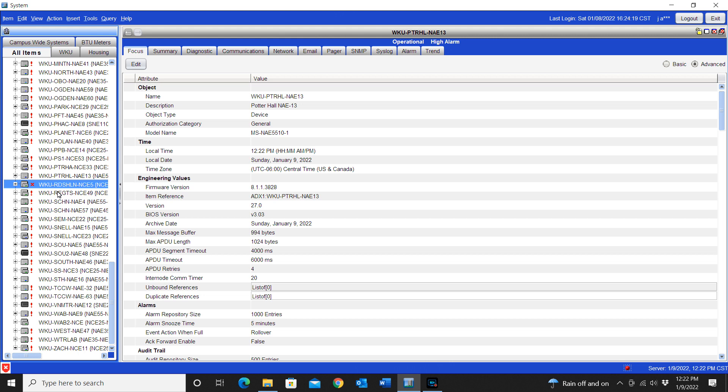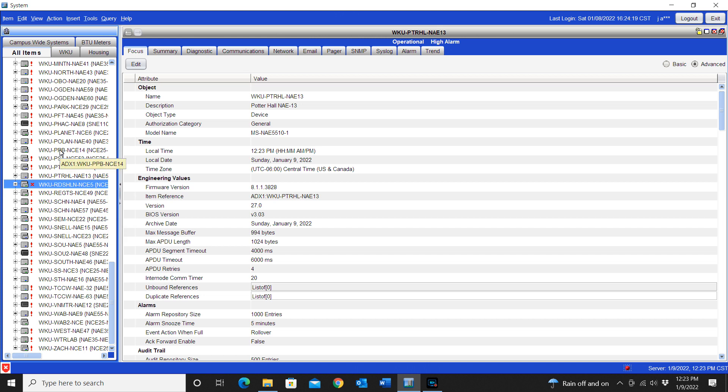Now one thing that we noticed when we fought this issue, we began fighting it when we first went to Metasys 11. And one of the things that has happened since then is any changes to a device's IP address, the device will come up as a red X. We are able to browse to the device from the server, and after verifying that the device can communicate with the server by browsing to it, we would then check the hosts file to make sure that the IP address is correct in that hosts file as far as what it thinks the device IP address should be.